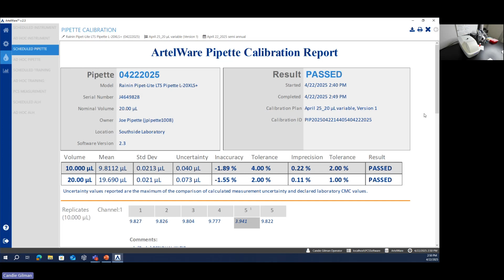It's not included in the final calculation statistics, but it is showing on the report to show that a redo had been performed. If I continue down, you can see all of the information that I had entered in about the environment, everything that I scanned for solutions and vials with the system. That gives me full traceability to all the items that I used for this pipette calibration. The same type of workflow is used for operator assessments. You'll see all of the same information. The operator comments, remember I entered a comment about changing the seal on the O-ring. That's also on this report.